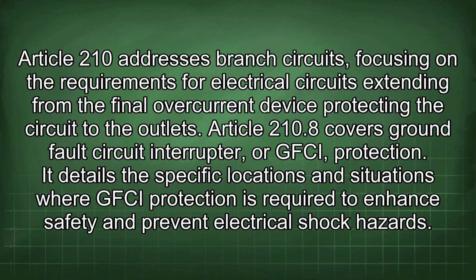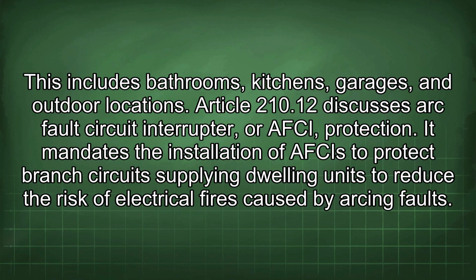Article 210 addresses branch circuits, focusing on the requirements for electrical circuits extending from the final overcurrent device protecting the circuit to the outlets. Article 210.8 covers ground fault circuit interrupter, or GFCI, protection. It details the specific locations and situations where GFCI protection is required to enhance safety and prevent electrical shock hazards. This includes bathrooms, kitchens, garages, and outdoor locations. Article 210.12 discusses arc fault circuit interrupter, or AFCI, protection.